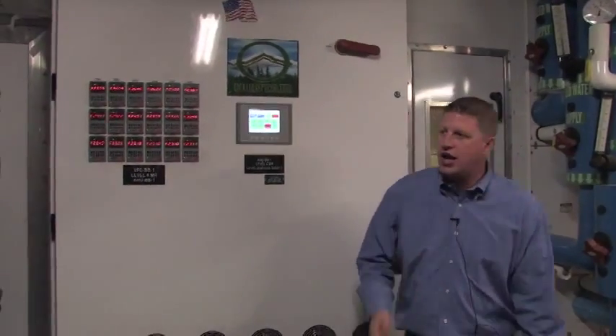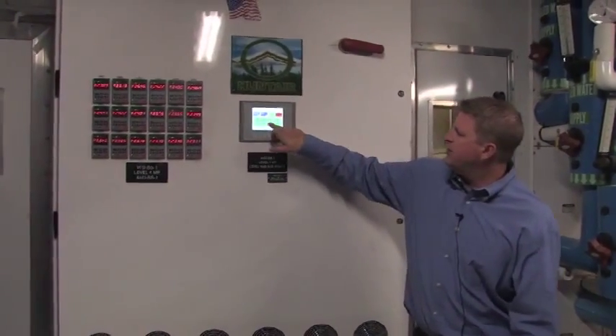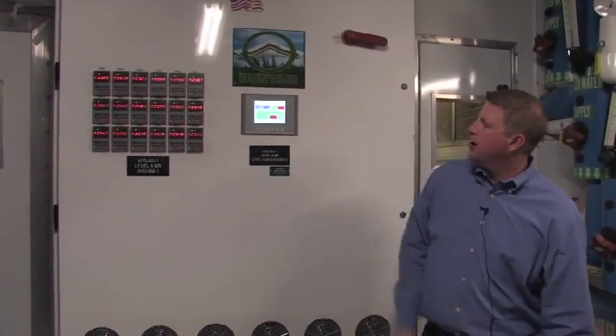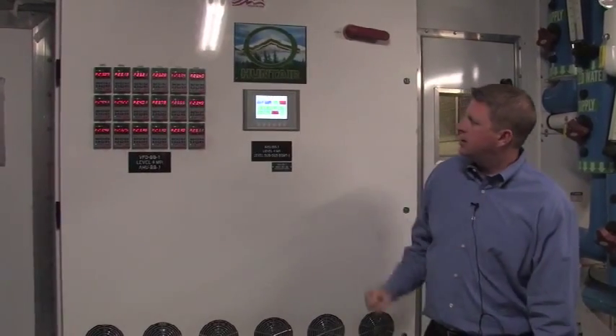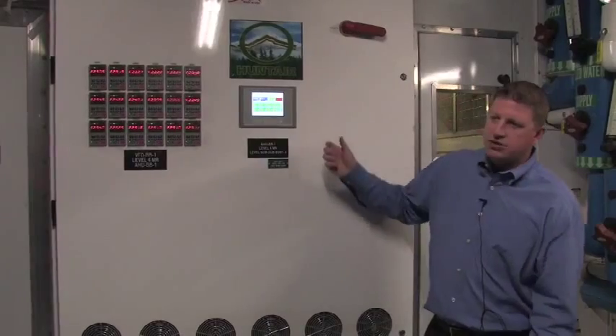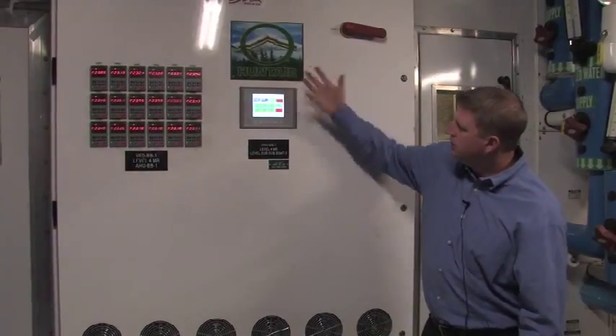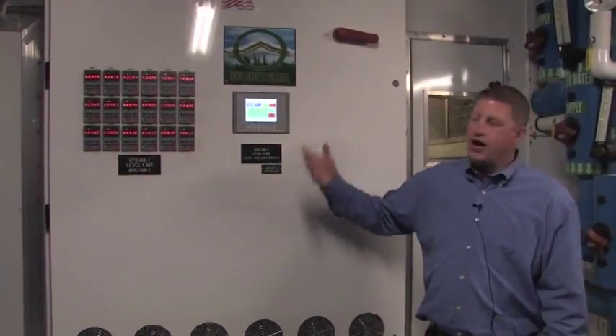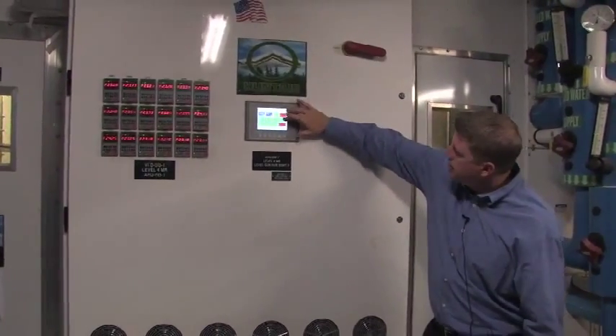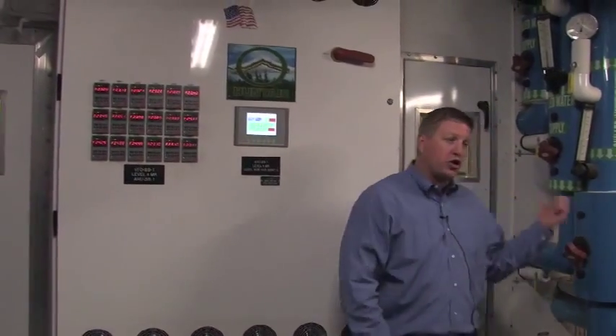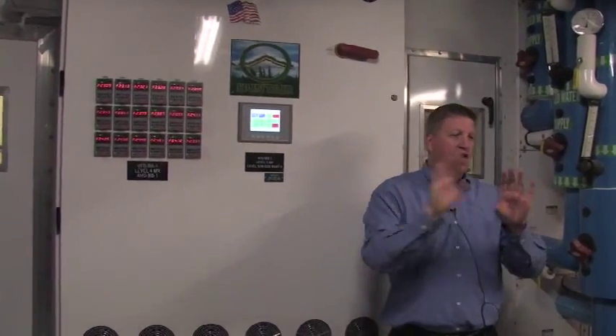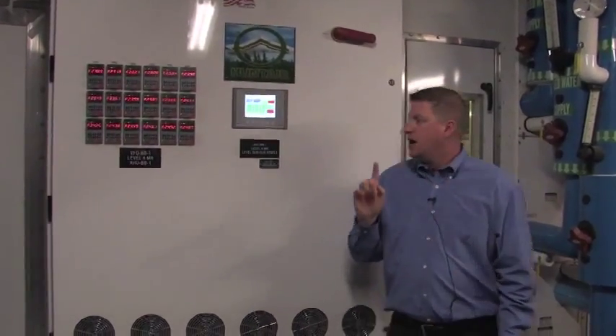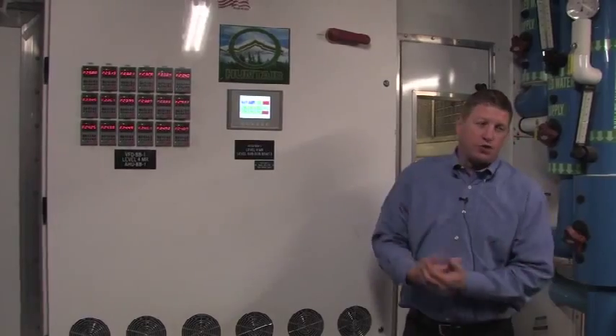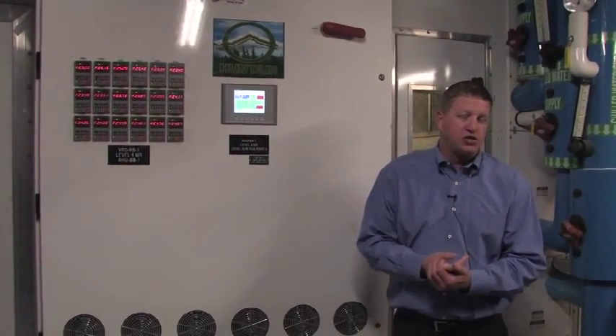You're not necessarily going to know what it is, but I could say, okay, it's not 7. Sound didn't go away. Now I'm going to hit 8. Wait a second. Sometimes it takes a couple. There you go. Go through 8. Nope, not 8. Go through 9, and that is shutting off. And you can look in the backdraft dampers to verify it. They will be closed. Now, that's what I'd say is your first responder. That's just to diagnose it.